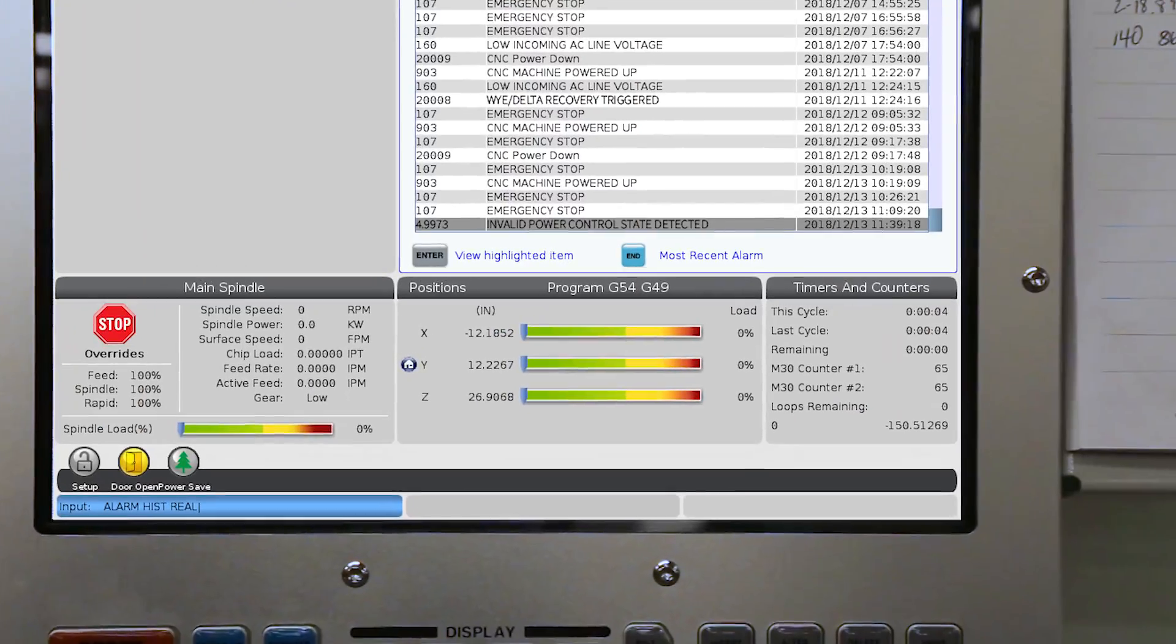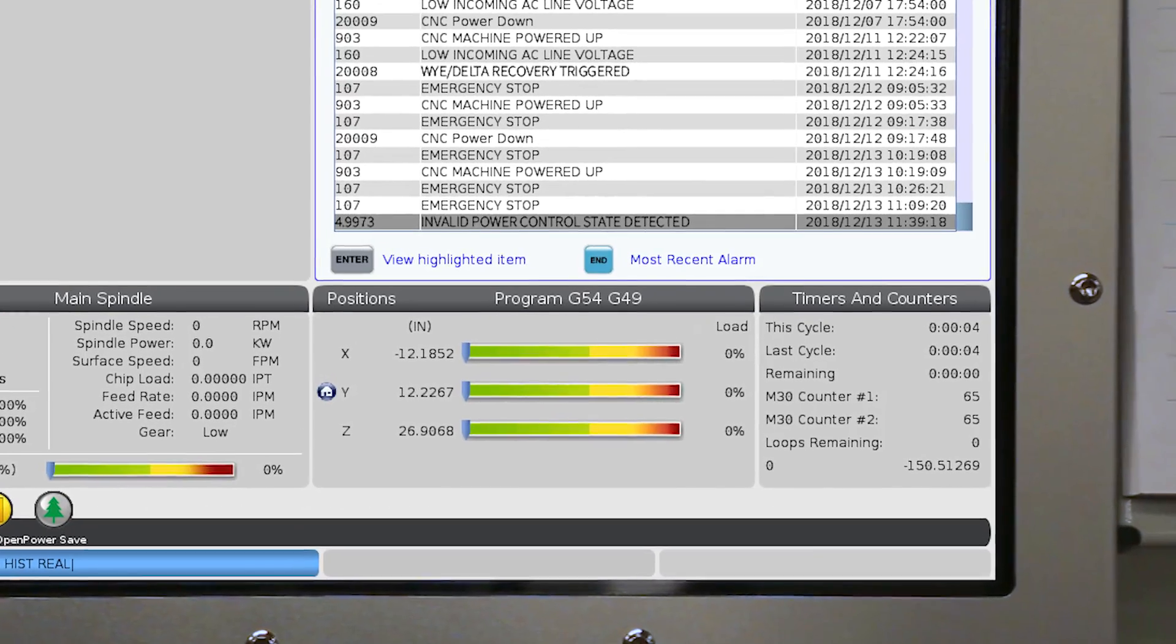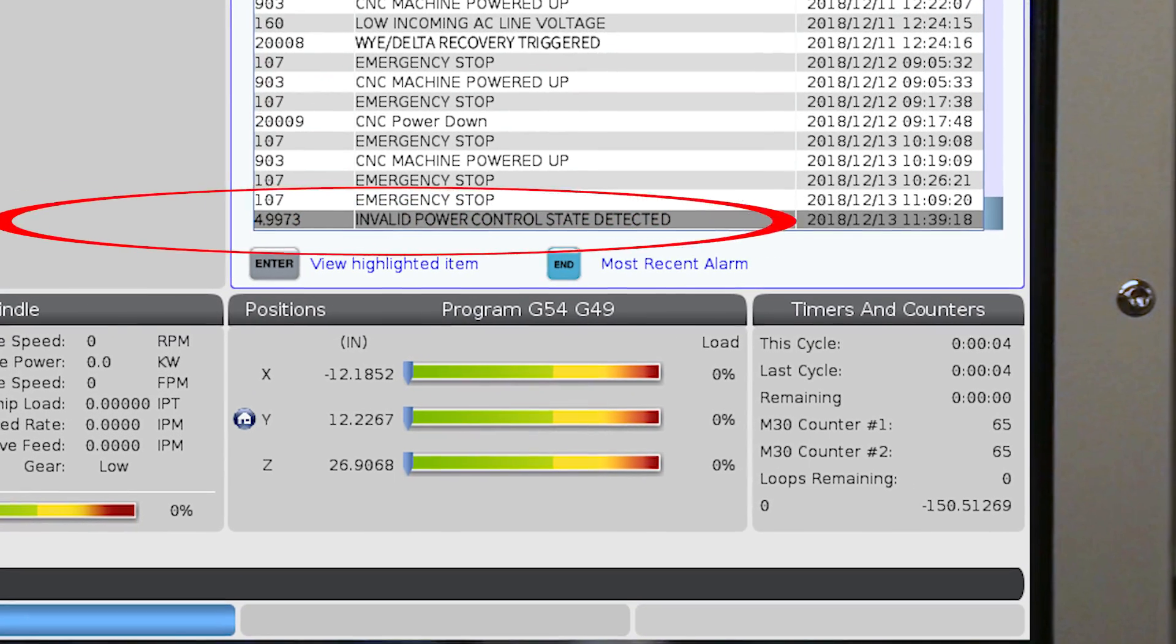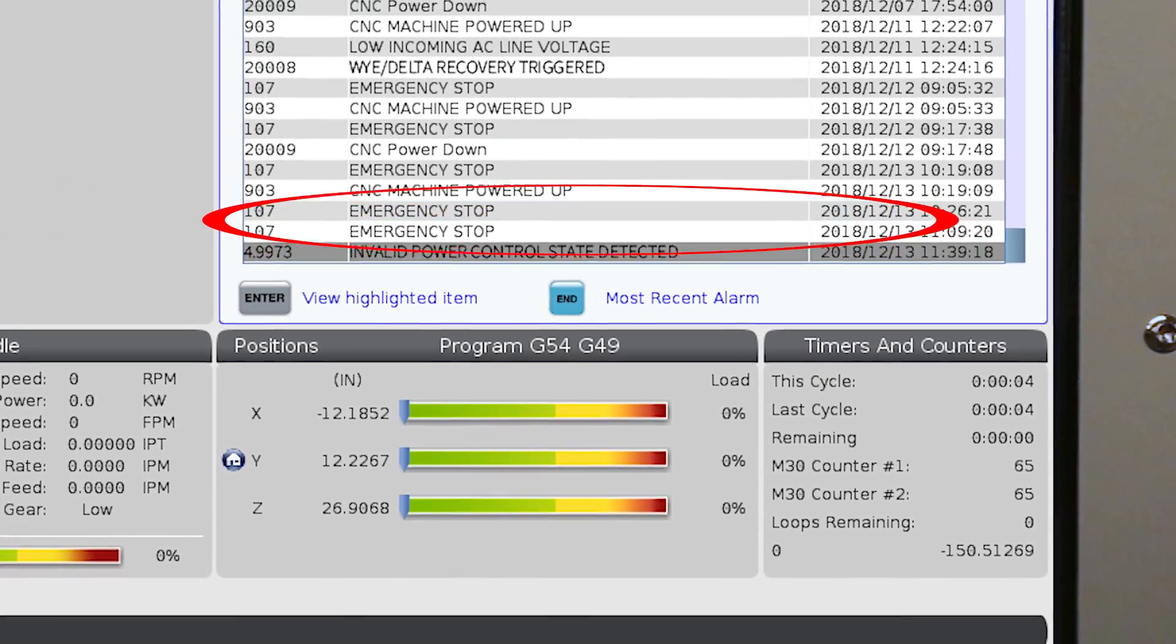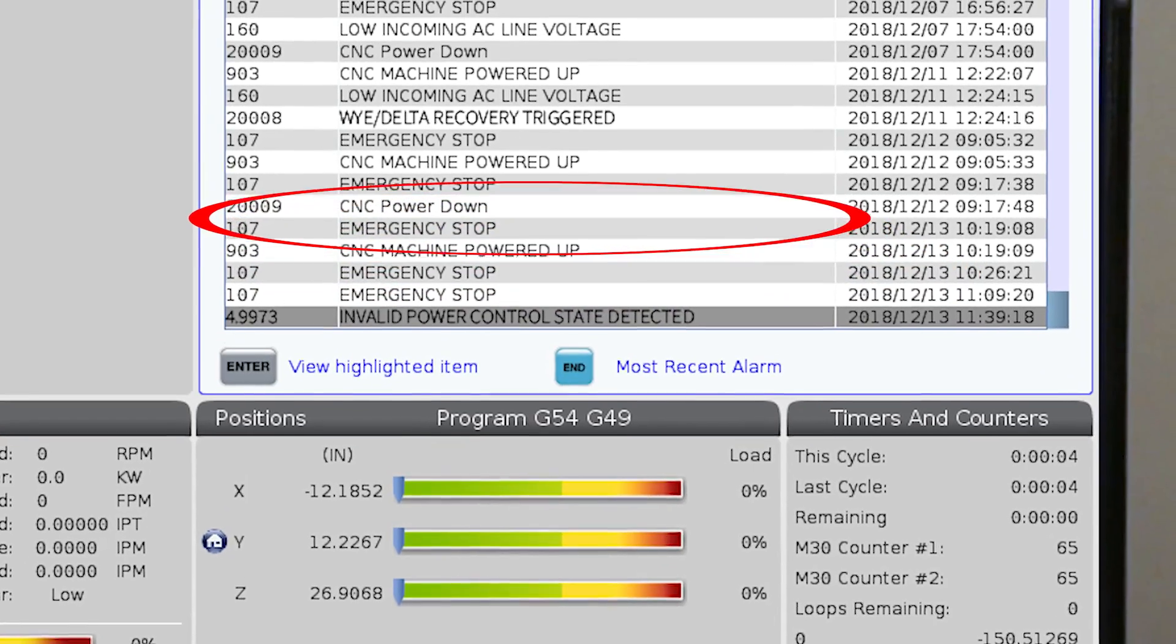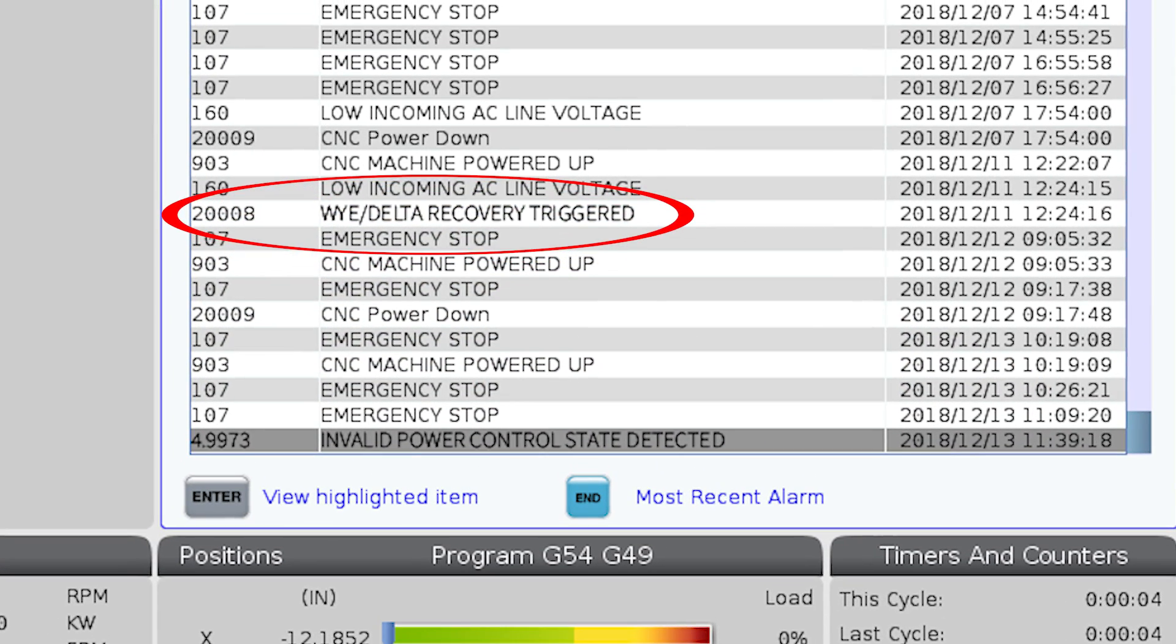If you see alarm 49973, or if you find a code 20008, these can be an indication there's a problem with the Y-delta contactor, but the more likely cause for these alarms is unstable external power coming to your machine.